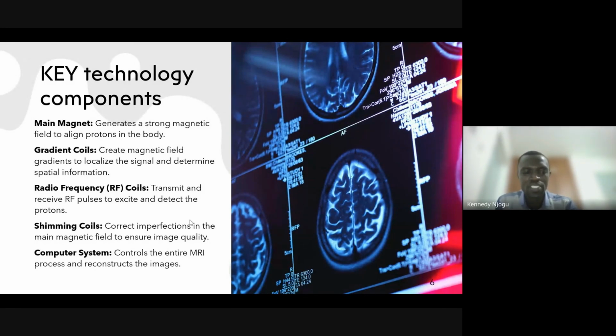And then there is an important part which we call the shimming coils. The shimming coils help correct the imperfections in the main field. Shimming is where you try to make the main field homogeneous. The field is in 3D shape and has lines, so the shimming enables the lines to be smooth and curved instead of wavy. The shimming can be either passive, or you can actually use metal pieces.